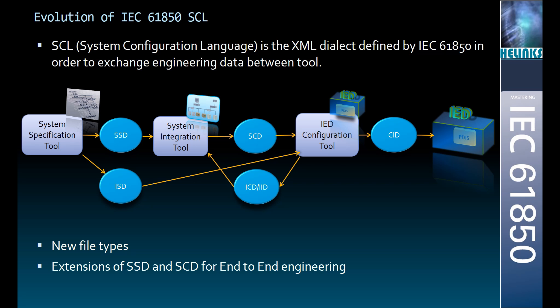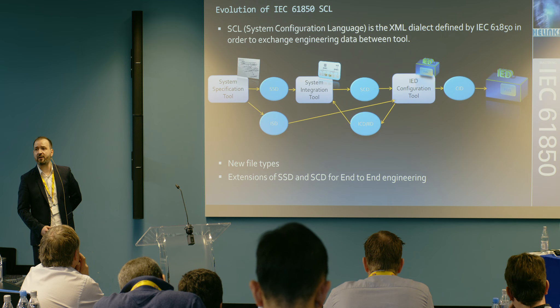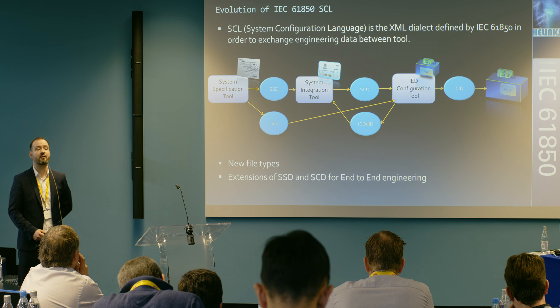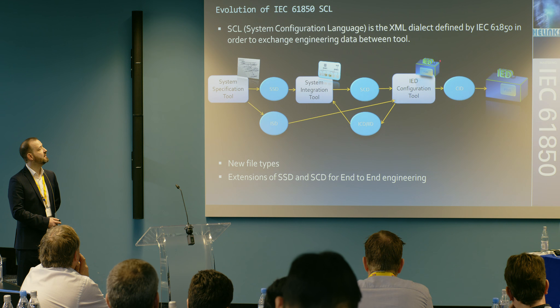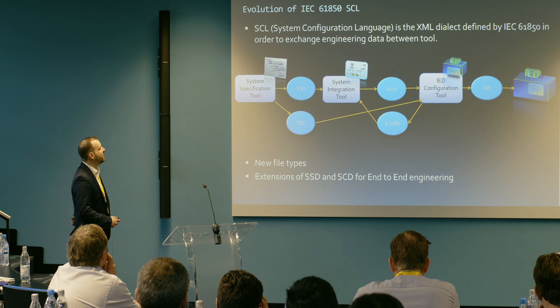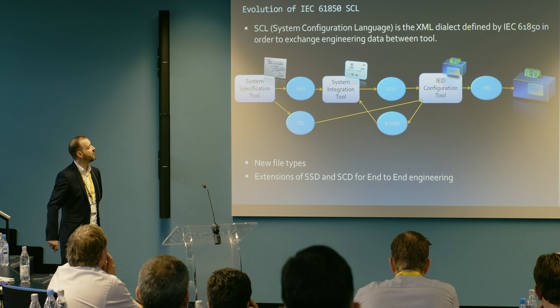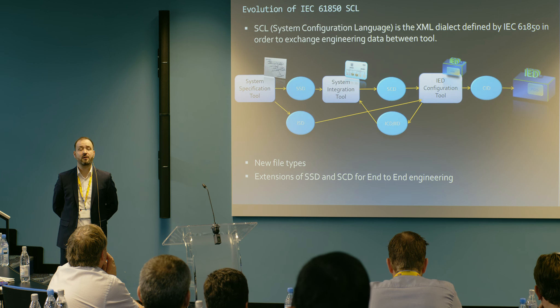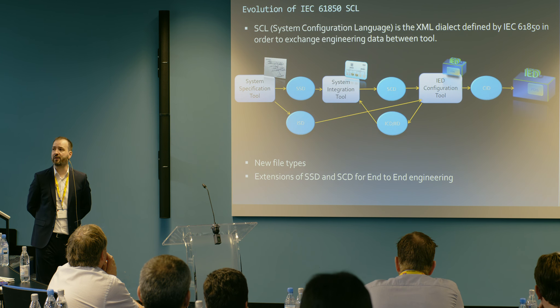The System Configuration Language is the XML dialect that we use to exchange data between tools and also in a human-readable format. The three major players that want to exchange data are the system specification tool, system integration tool, and the multiple IED configuration tools. Each of these file types used during the engineering process contain a subset of the possible information that SCL can contain.